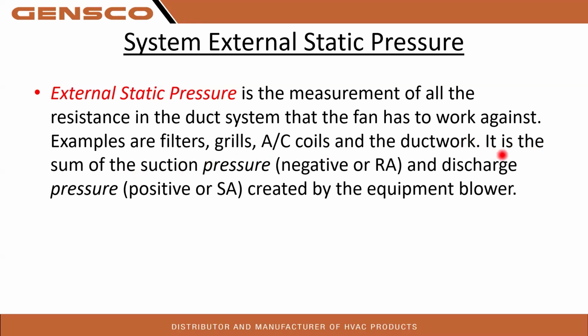Okay, so static pressure is the sum of all the suction pressure, or negative, in the return air, and discharge pressure, positive, in the supply air. So negative in the return air, you're pulling in, and discharge pressure positive in the supply air, created by the equipment blower.